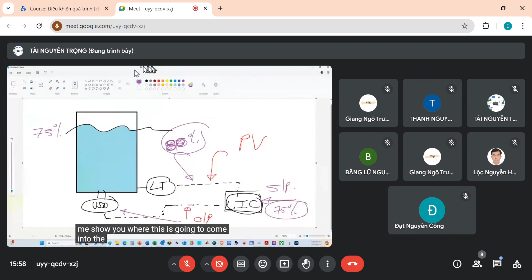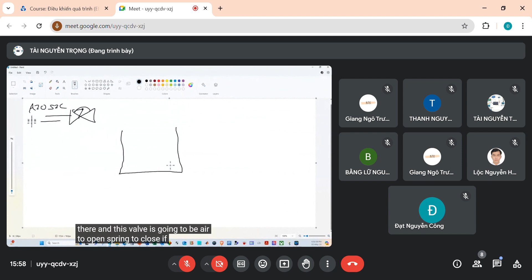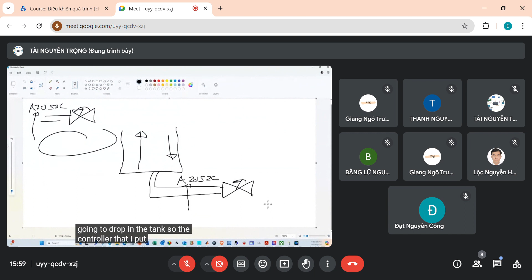As you know, I don't do PowerPoint slides, I like to draw my own pictures. Say I have a tank with a valve, and this valve is air to open, spring to close. If I give this valve air, it opens up and the level inside the tank rises. What if I put the same type of valve somewhere else, also air to open, spring to close? If I give it air, it opens up, but now my level drops in the tank. So the controller I use there must be different from the controller I use here. One needs to be direct and the other needs to be reverse control for this to work.